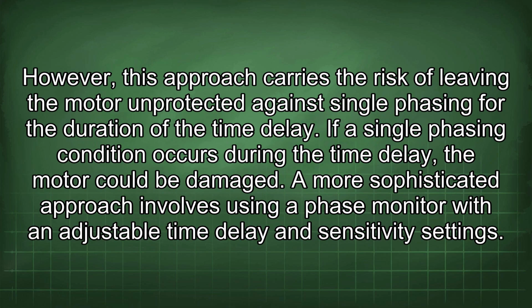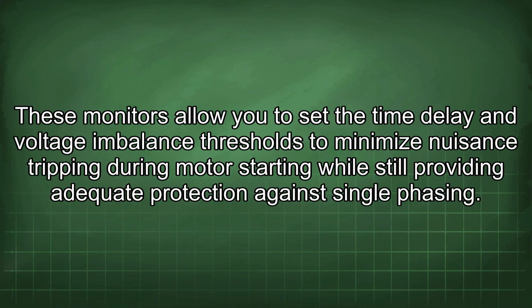However, this approach carries the risk of leaving the motor unprotected against single phasing for the duration of the time delay. If a single phasing condition occurs during the time delay, the motor could be damaged. A more sophisticated approach involves using a phase monitor with an adjustable time delay and sensitivity settings. These monitors allow you to set the time delay and voltage imbalance thresholds to minimize nuisance tripping during motor starting while still providing adequate protection against single phasing.